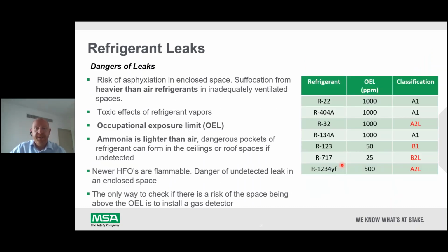So, the dangers of the leaks, and what levels of leaks are dangerous. There is the asphyxiation risk in an enclosed space and the toxic effects of the vapors. We have occupational exposure limits which are developed globally at certain parts per million levels. So any gas leak above these levels becomes very dangerous to the occupants of that area. You can see here the HFCs and HCFCs are generally 1,000 ppm. Above that is a danger level. Some of the older refrigerants, such as R123, which is used in a lot of large water-cooled chillers, are toxic. So 50 ppm of that is dangerous. And then we have ammonia, where above 25 ppm starts to get dangerous.